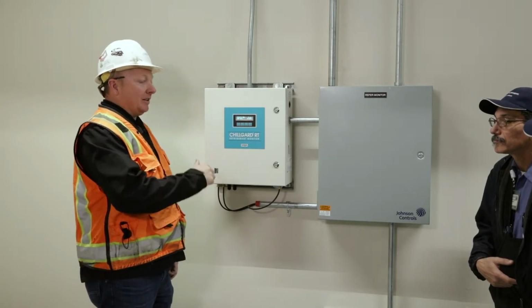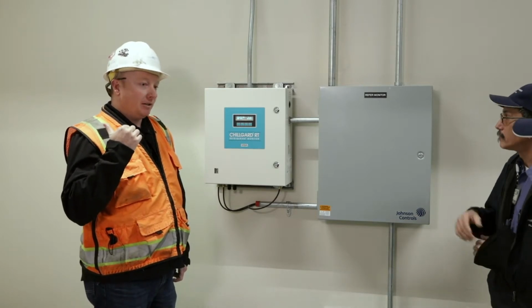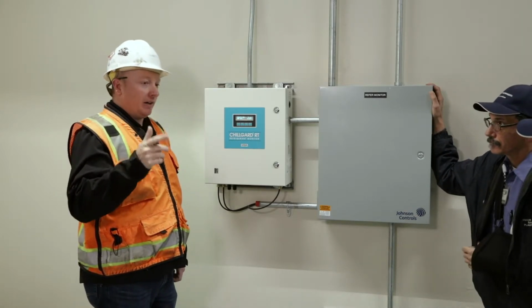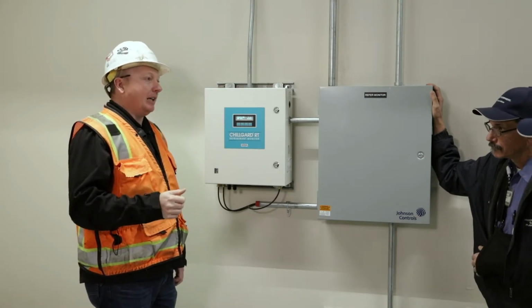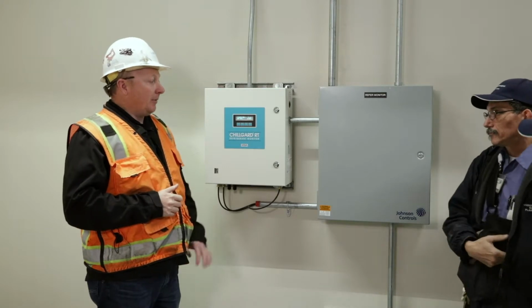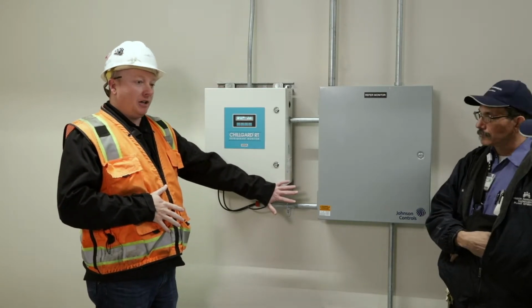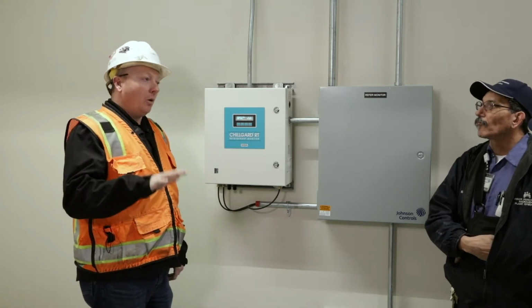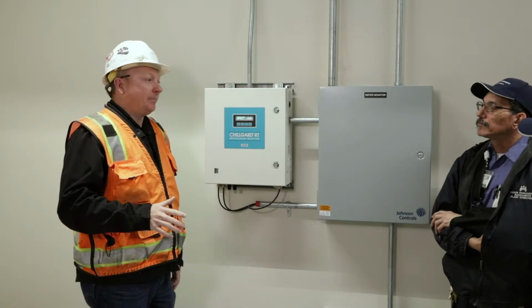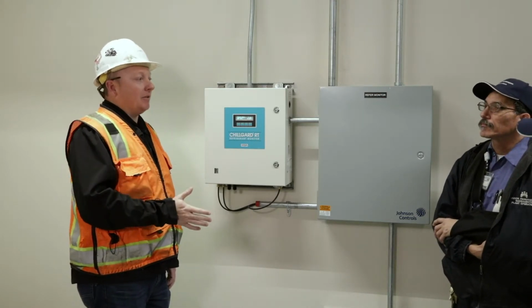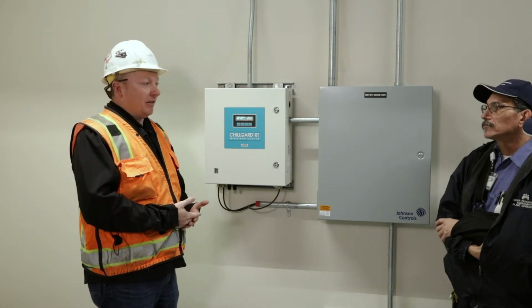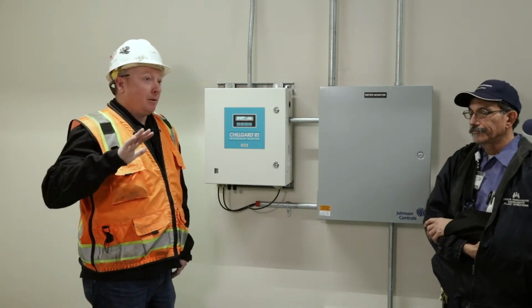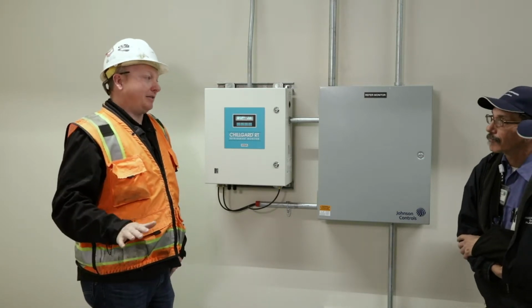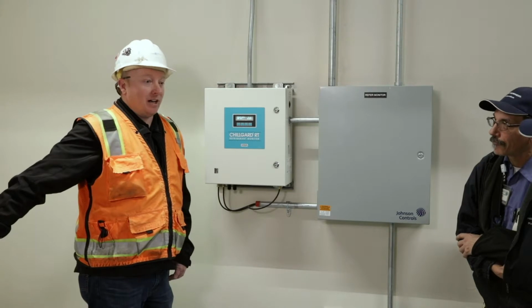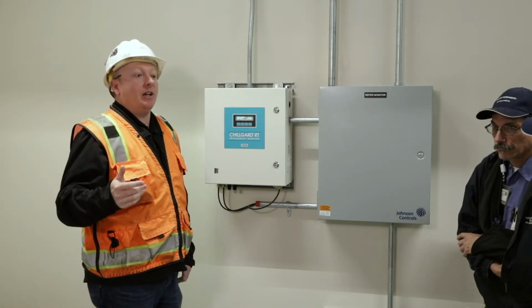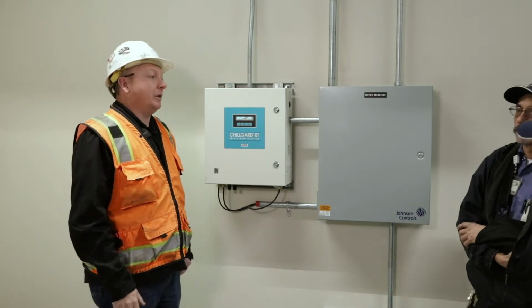The only other part of this is there is also a key switch out there, only at this entrance, for the purge fan. So it's got a HOA basically, and if you leave it in auto, it's going to come on if we have a leak detection in here, or if someone does one of the break glass switches, or it'll also come on and off for temperature control. It's not like what you guys have at the Central Plant at Morse Avenue, where we have a continuous fan that's always on, and then we have another purge one. Normally in here, there is no fan running unless we have an alarm or it's cold enough outside, we don't need the fan coil, and we can just turn the exhaust fan on and just draw in outside air for cooling.